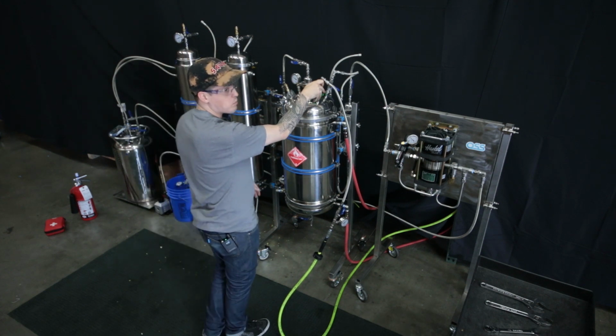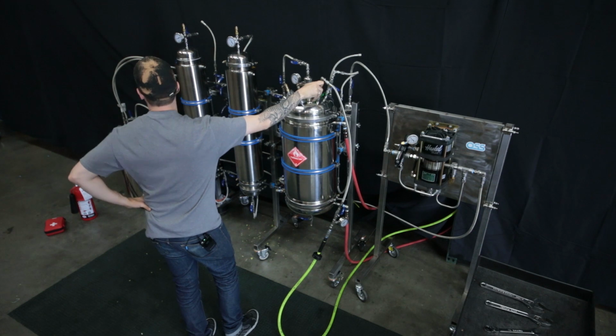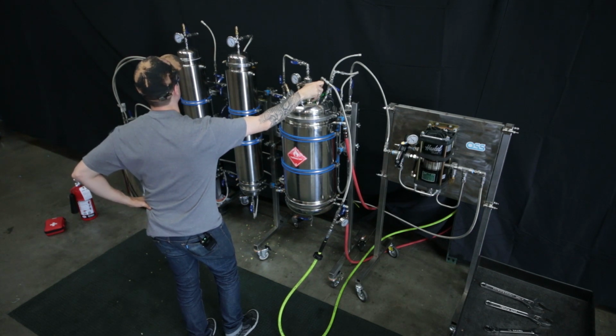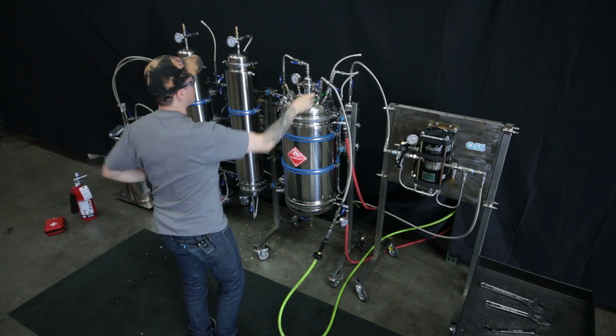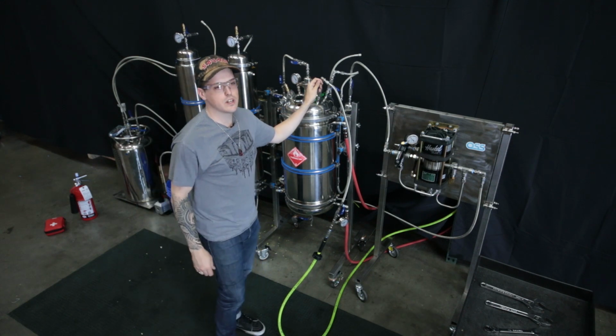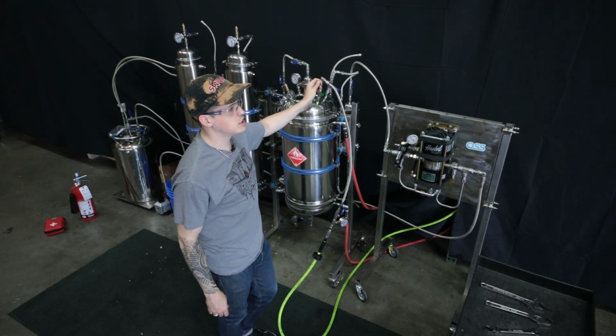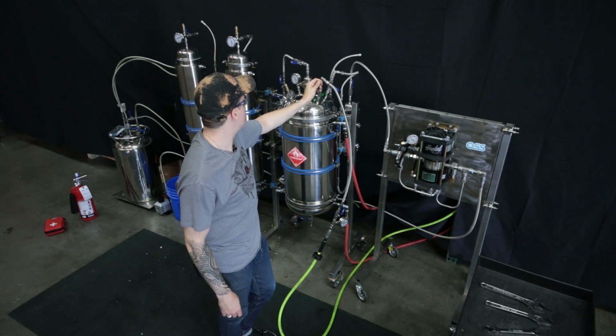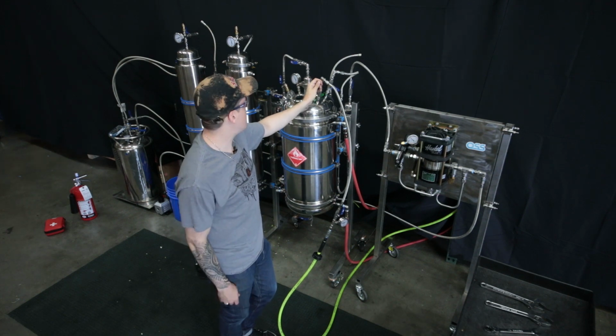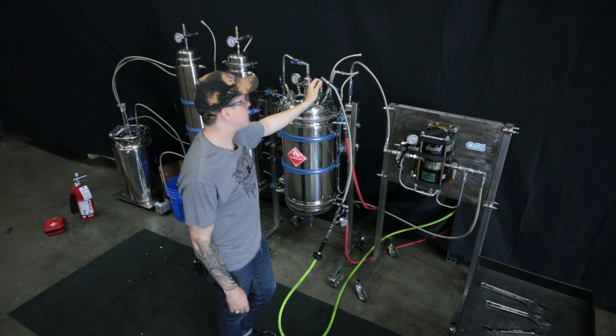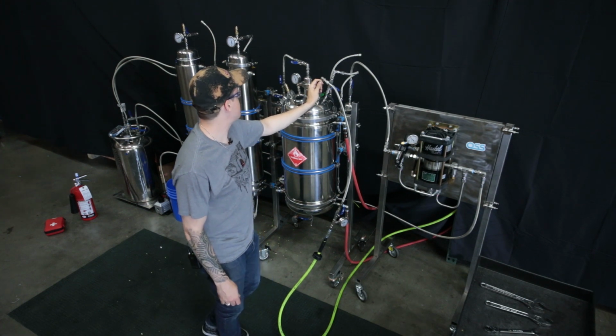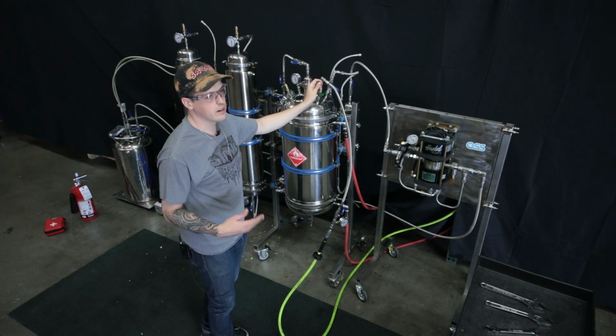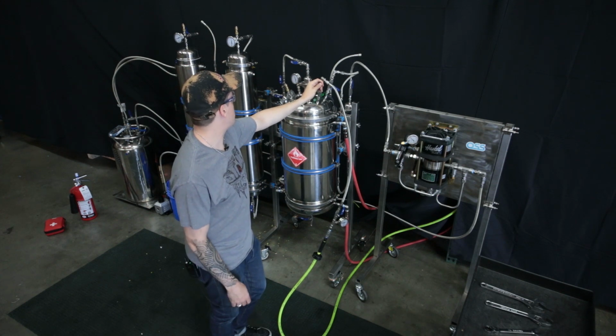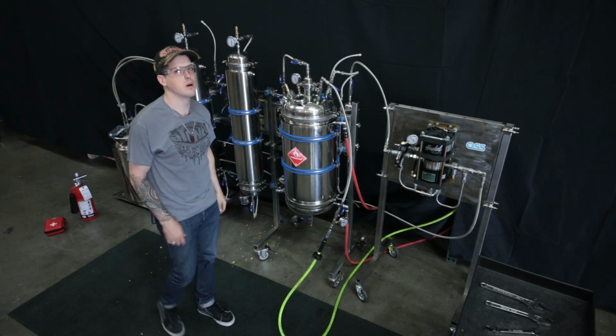In a second, you're probably going to hear the compressor turn on. So we're at 40. 50. Normally when we do this for an engineer or for final certification for a licensed facility, we'll take it to 100 psi. For today, we're just going to take it to 60 psi. It's plenty safe. We'll probably never see over 60 psi during the entire process.